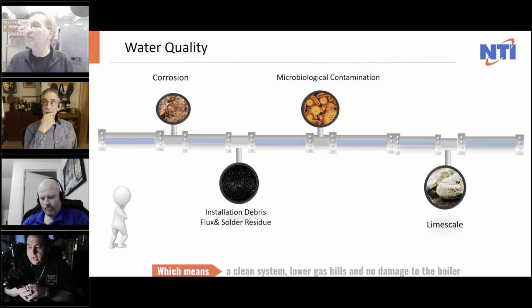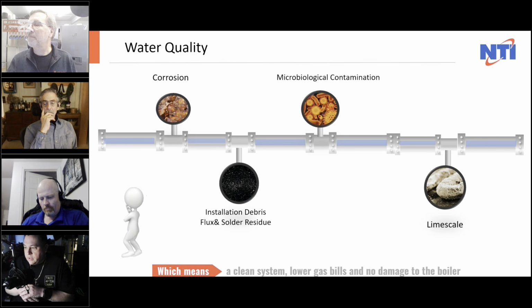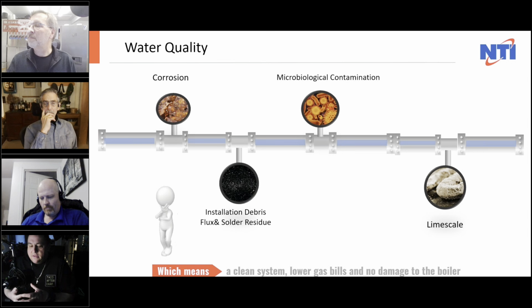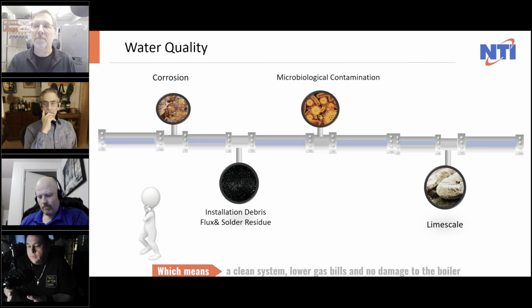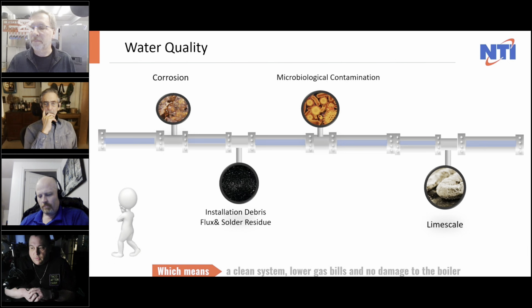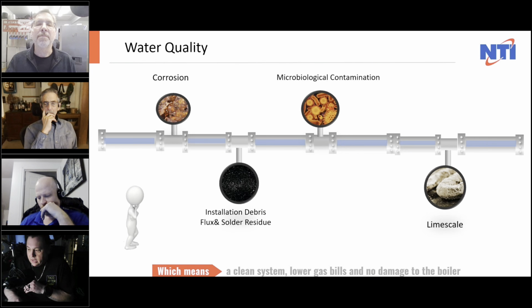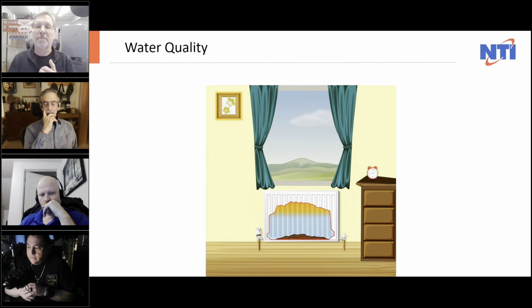Other things like large magnetite and debris are the biggest hurdle we have, and one of the problems we always experience with a high efficiency boiler. Once you take it out of solution and heat it up, it sits down in the bottom of that heat exchanger and hardens as the circulator moves around it, causing a concrete-type condition inside the heat exchanger, which is an issue when it comes to flow. It can also affect other things in the house, like the cast iron rads you may have.